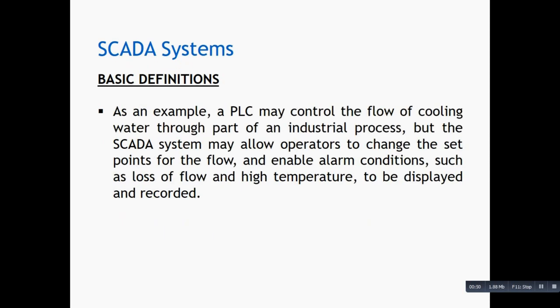For example, a PLC may control the flow of cooling water through part of an industrial process, but the SCADA system may allow operators to change the set points for the flow and enable alarm conditions such as loss of flow and high temperature to be displayed and recorded.